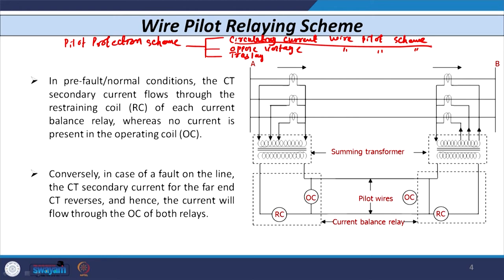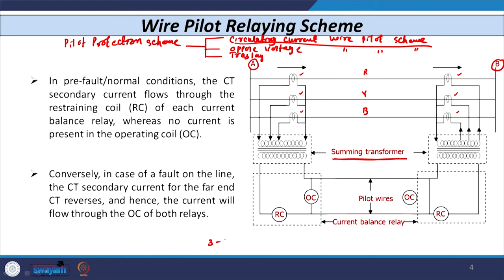Here the schematic diagram of the circulating current wire pilot relaying scheme is shown. There are two buses, bus A and bus B, between which a single-circuit three-conductor transmission line (R, Y, B) is connected. At substation A, we have three line CTs — one per phase — whose secondary signals are given to a device known as the summing transformer. The same arrangement exists at substation B. The summing transformer converts any three-phase signal into a single-phase quantity.